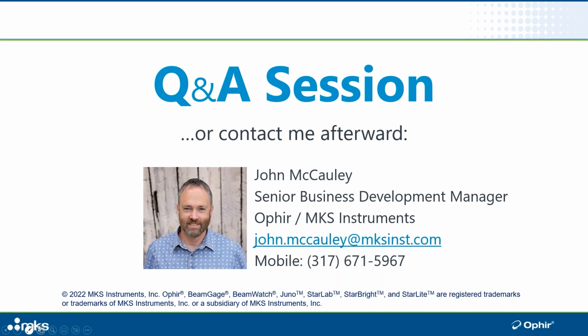Yes, that's a good question also, because this is one I get quite a bit: how often do I measure laser power? And the bottom line is, with respect to the industrial lasers being used for part processing, it really is up to you. There really isn't a right or wrong answer. I've got customers who measure their laser three times a day, once a shift.